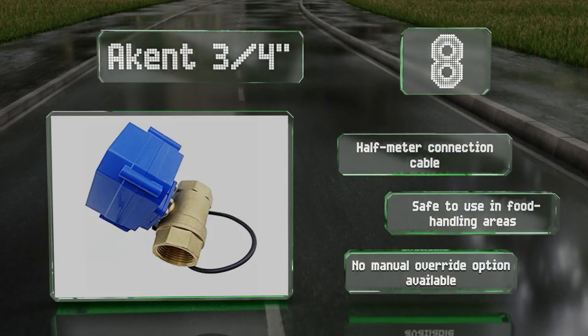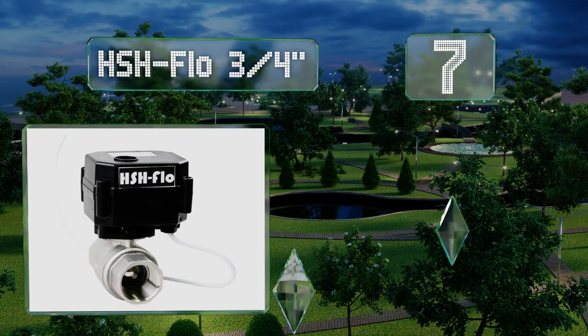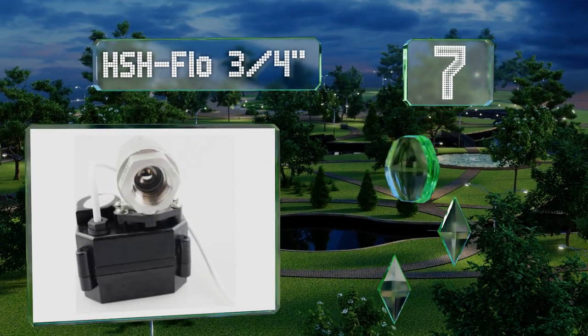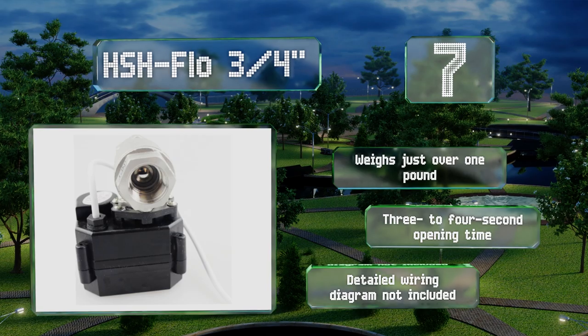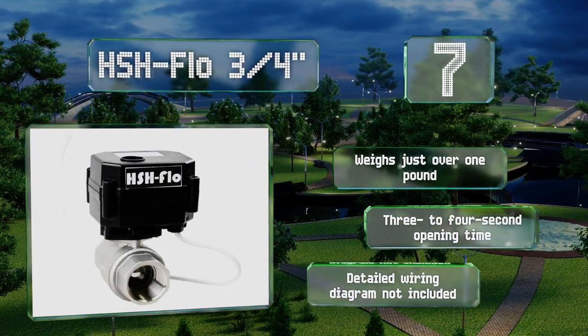At number 7, with a maximum tolerance of 145 psi, the HSH-Flo 3/4 inch has a higher pressure rating than most alternatives and is lead free, so it can be used with potable water. At a little over 5 inches tall, installation in tight spaces might be difficult. It weighs just over 1 pound and offers a 3 to 4 second opening time, but a detailed wiring diagram is not included.